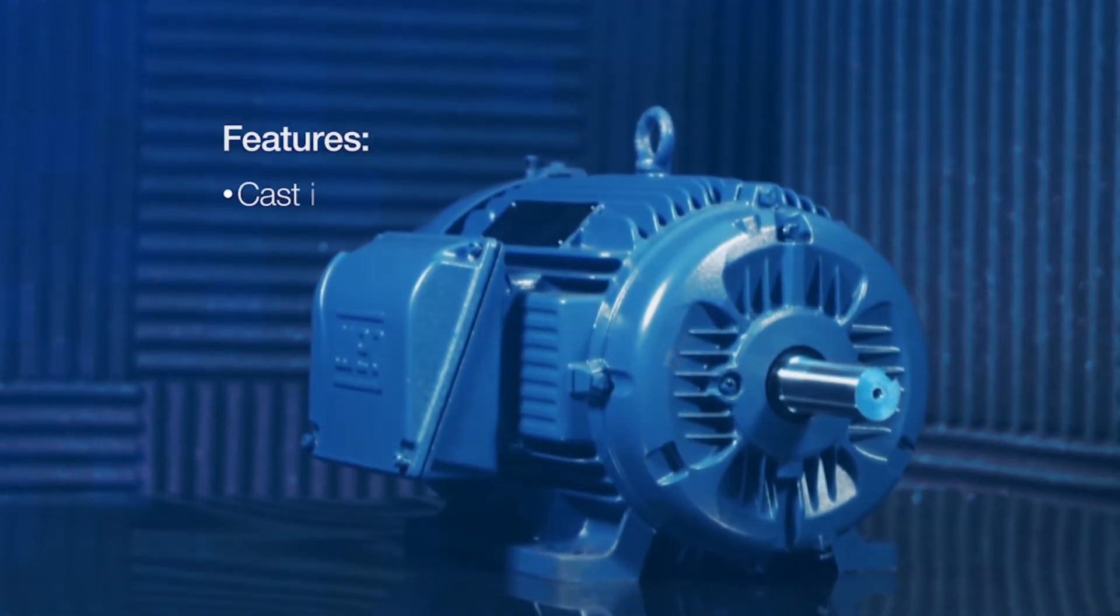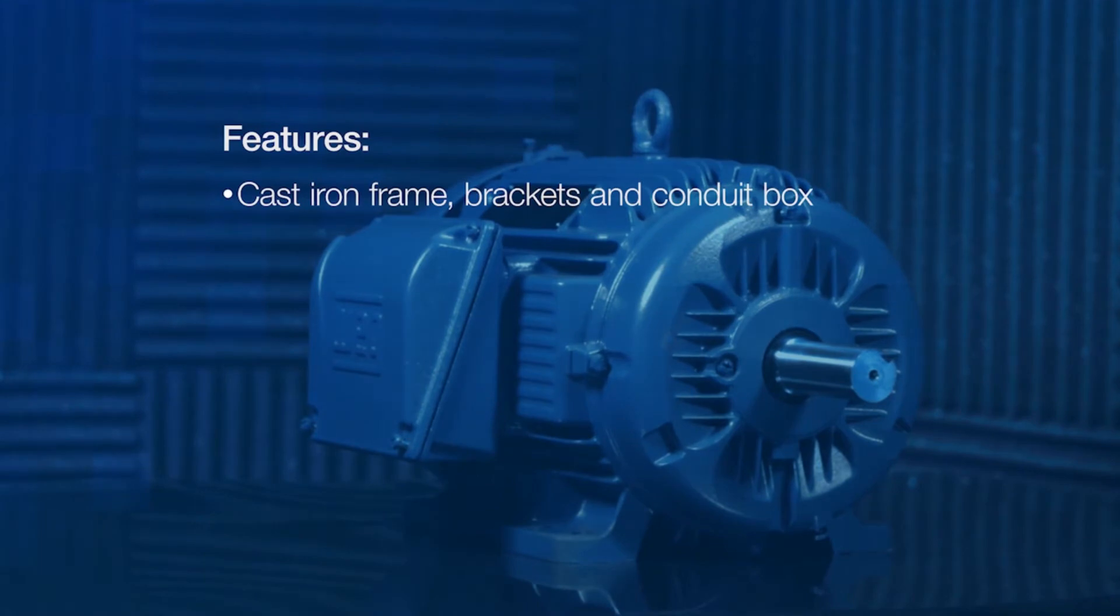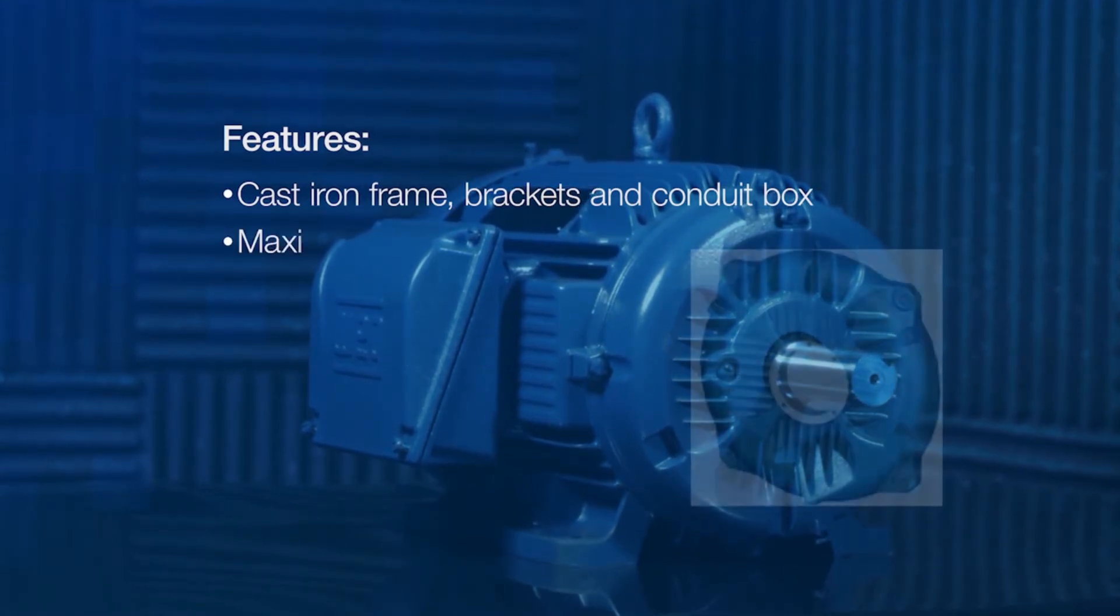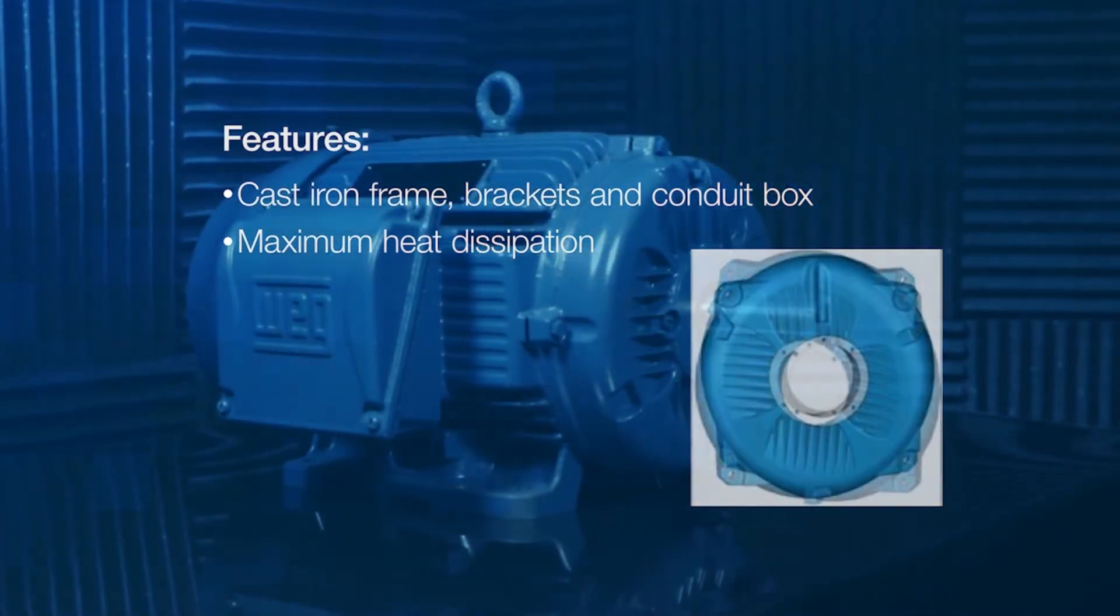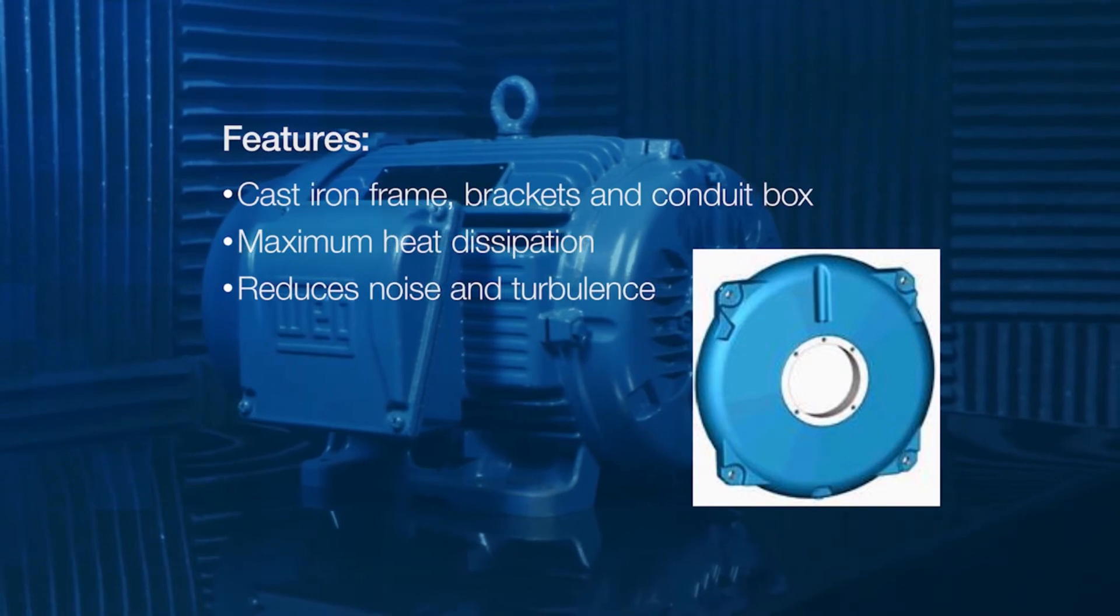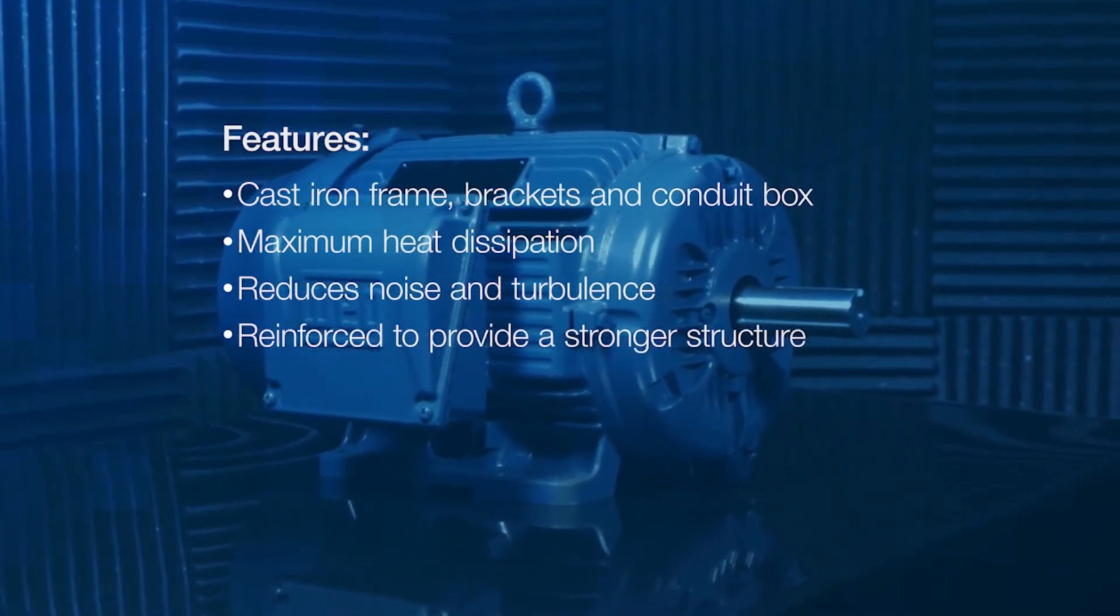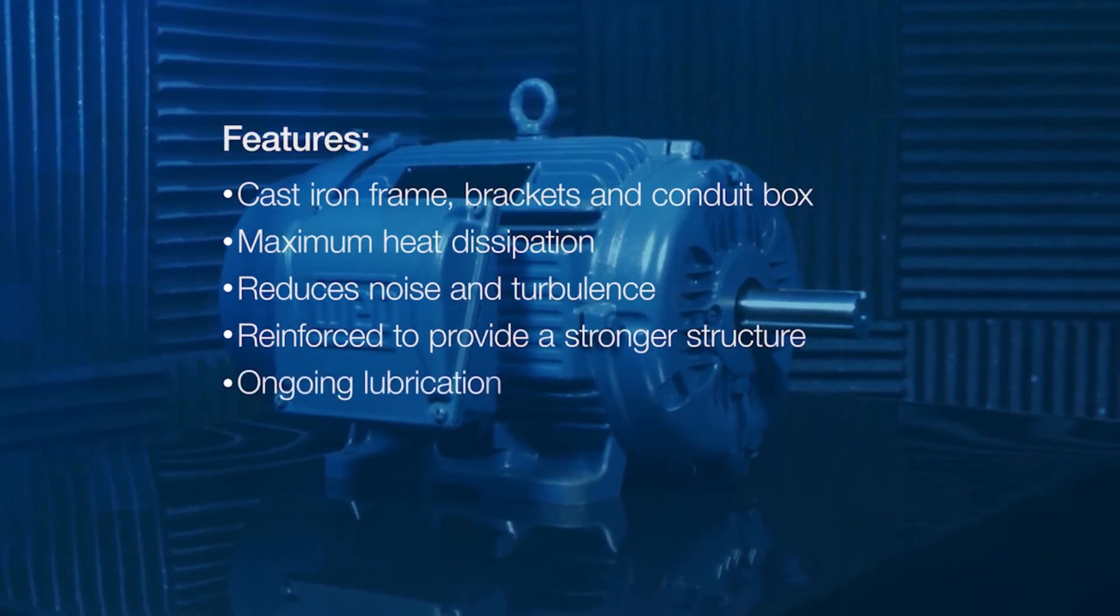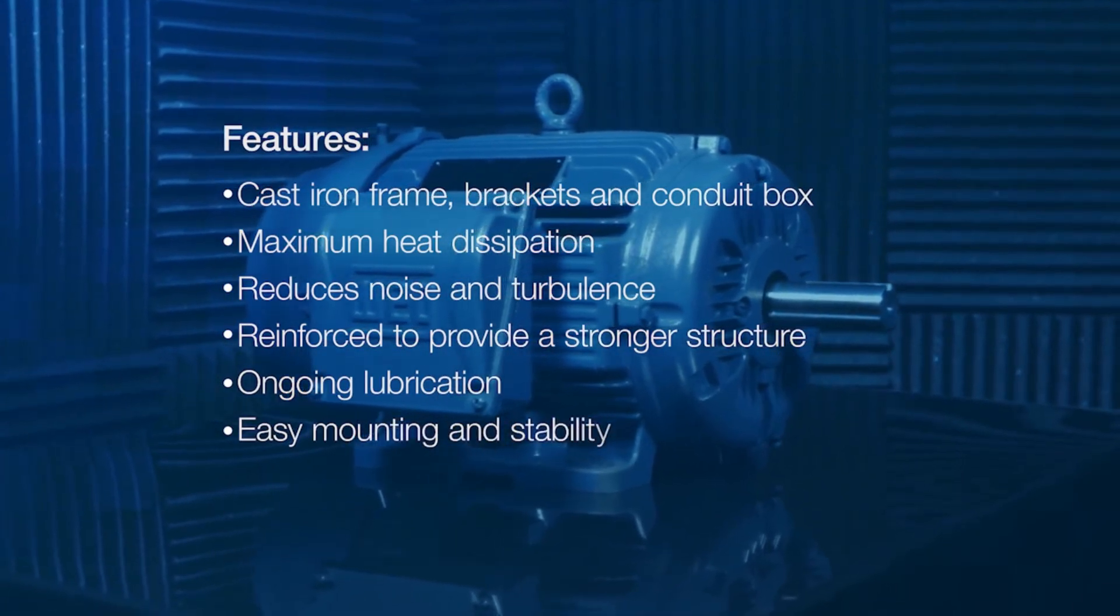Other features include an FC200 high strength cast iron frame, brackets and conduit box with a new end shield design. The drive end shield's fin design provides maximum heat dissipation, while the non-drive end shield's smooth area reduces noise. The bracket to frame bolt area is reinforced to provide a stronger structure. Integral grease channels contribute to ongoing lubrication. Solid feet mean easy mounting and stability in high vibration applications.